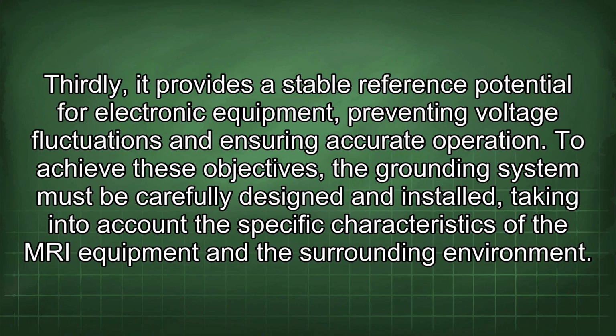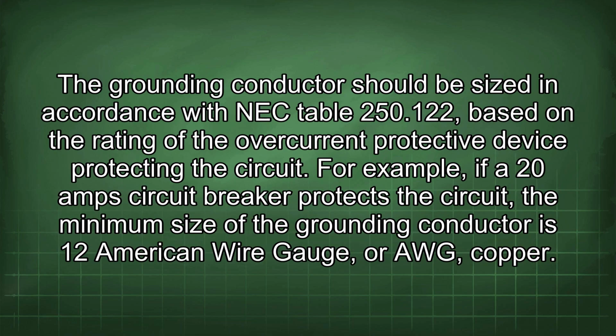Thirdly, it provides a stable reference potential for electronic equipment, preventing voltage fluctuations and ensuring accurate operation. To achieve these objectives, the grounding system must be carefully designed and installed, taking into account the specific characteristics of the MRI equipment and the surrounding environment. The grounding conductor should be sized in accordance with NEC Table 250.122, based on the rating of the overcurrent protective device protecting the circuit.